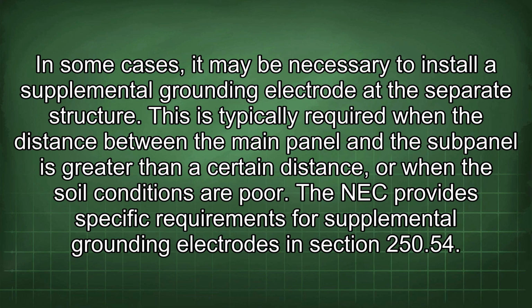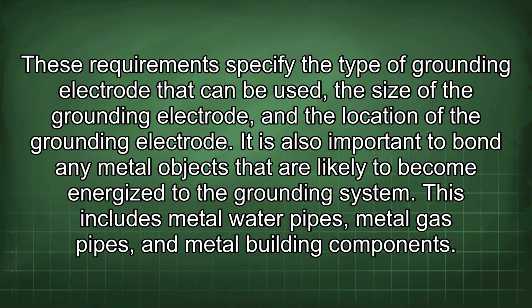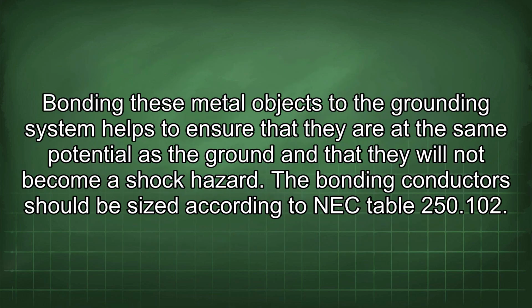The NEC provides specific requirements for supplemental grounding electrodes in section 250.54. These requirements specify the type of grounding electrode that can be used, the size of the grounding electrode, and the location of the grounding electrode. It is also important to bond any metal objects that are likely to become energized to the grounding system. This includes metal water pipes, metal gas pipes, and metal building components. Bonding these metal objects to the grounding system helps to ensure that they are at the same potential as the ground and that they will not become a shock hazard.